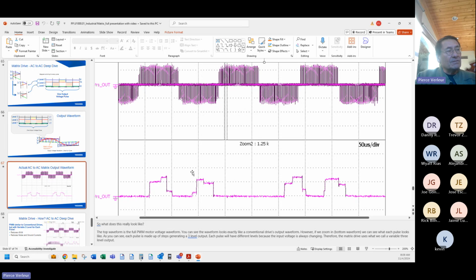Because again, we can get 3 levels of voltage at any instant in time off the 3-phase line. We switch it directly to the motor lead that we want. Motor winding 1, motor winding 2, motor winding 3. And our pulse is not full height. It's pulse amplitude modulated as well. Pulse amplitude modulation plus pulse width modulation means better switching to the motor from the matrix drive, better simulation of the analog function, less DVDT.